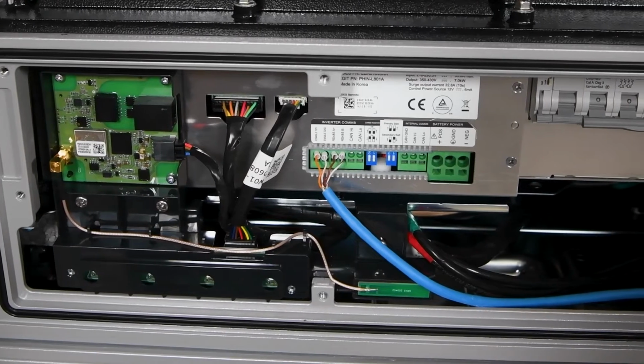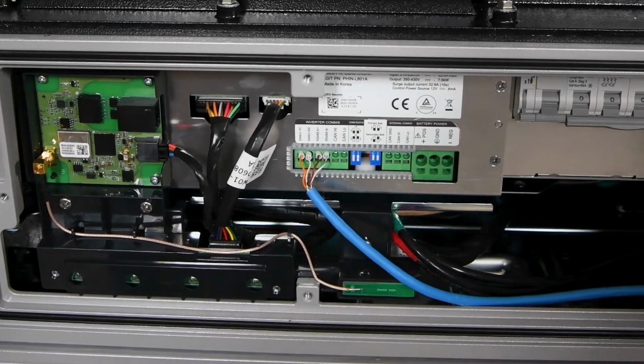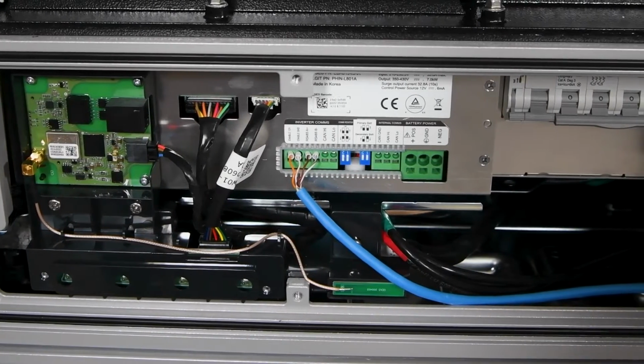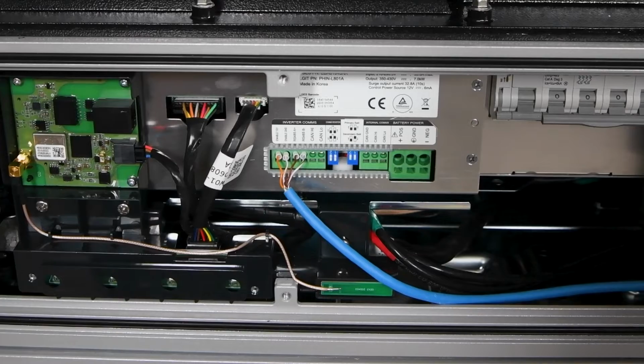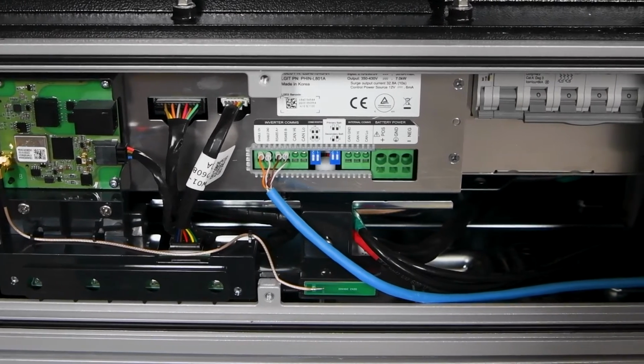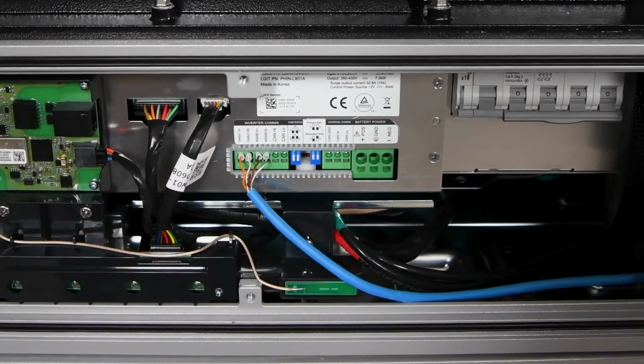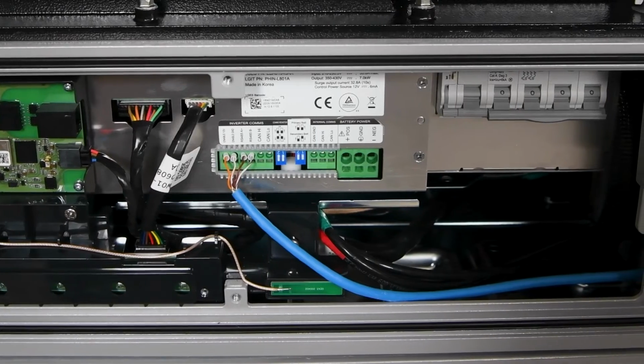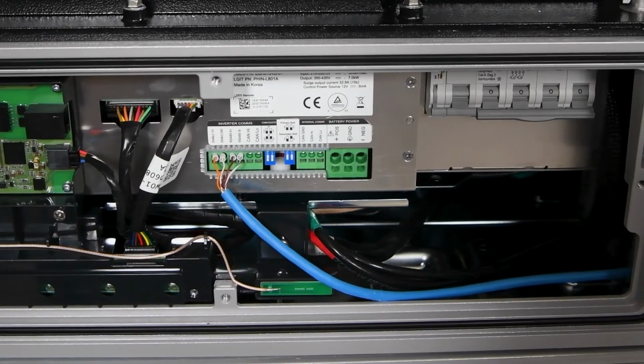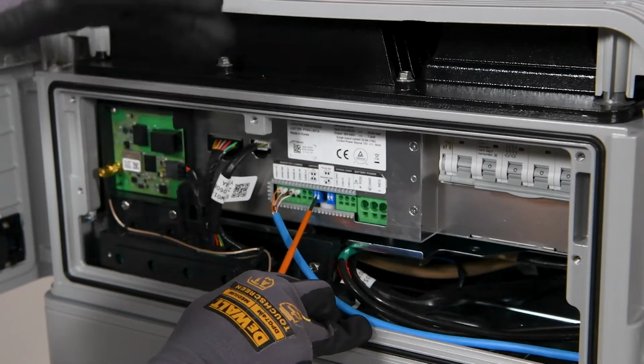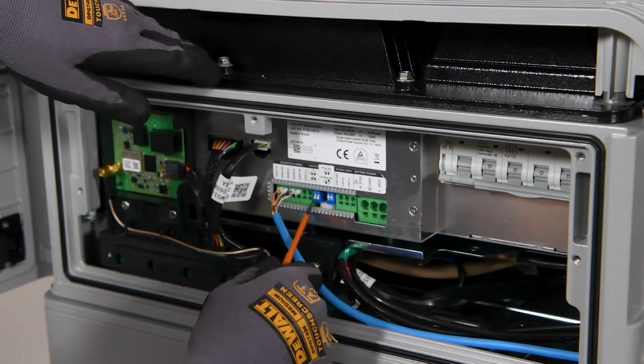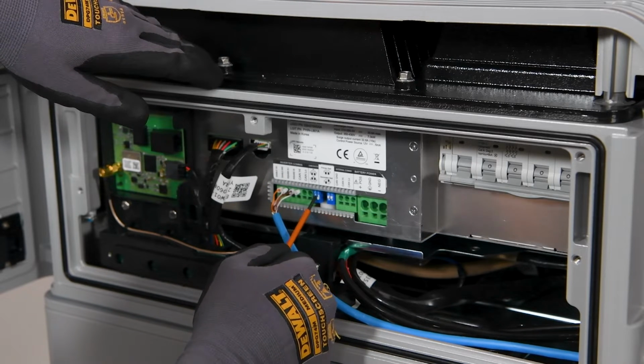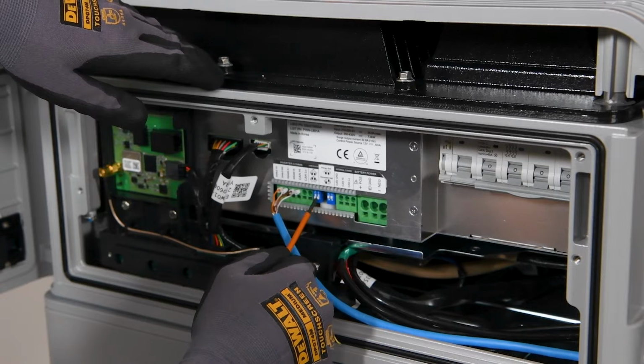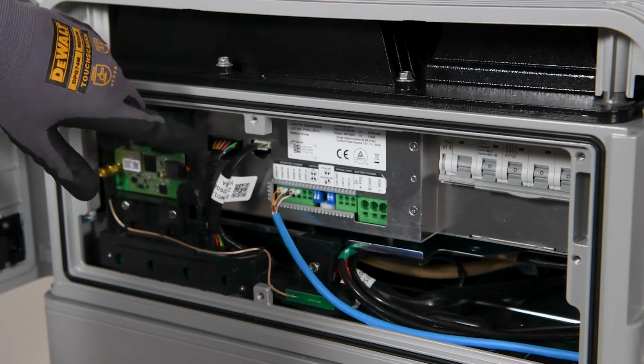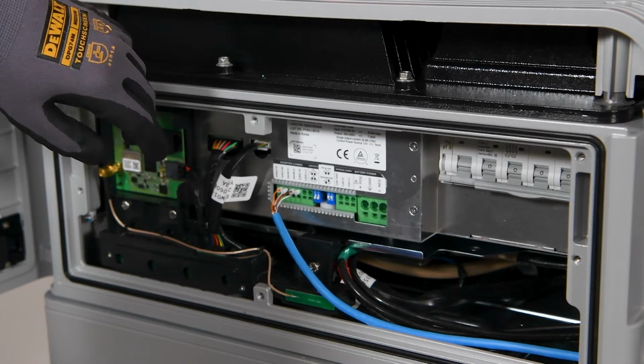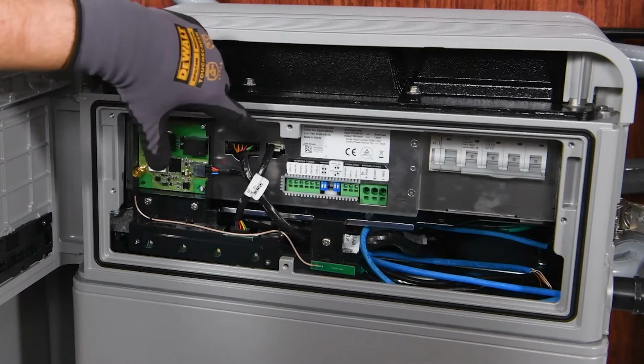An important note to make when adjusting the dip switches is if you're experiencing any communication issues, the reason for that may be due to the oil that reduces the amount of wear and tear on the dip switches getting in between the contacts of the actual dip switches and the relay. So if you're experiencing any communication issues, you can move the dip switches up and down 15 or 20 times to remove the oil and ensure that the relays and the contacts are making a good connection. We're at our secondary battery now.